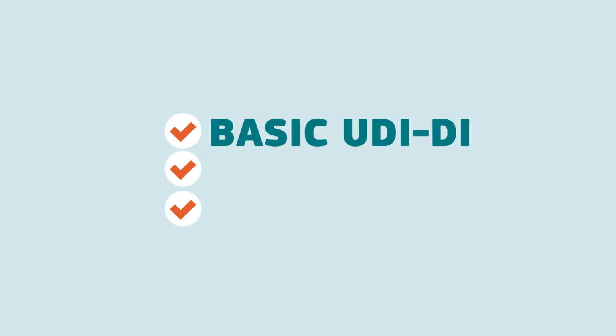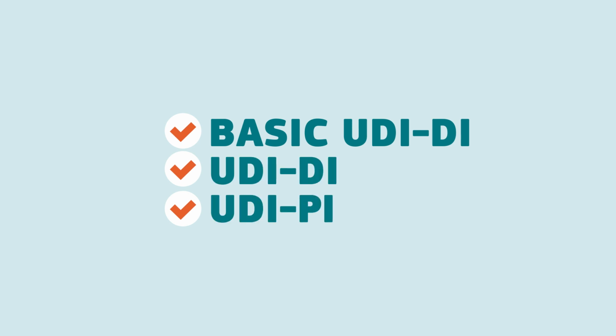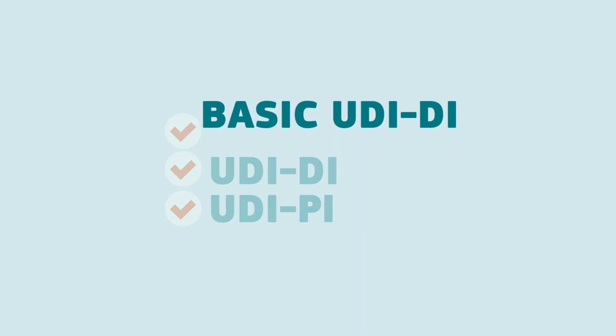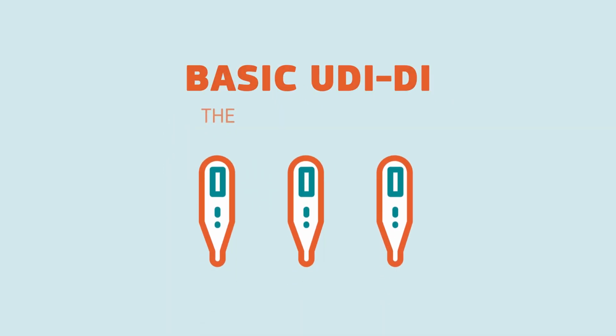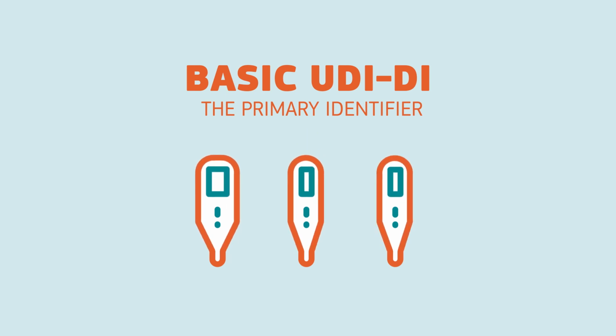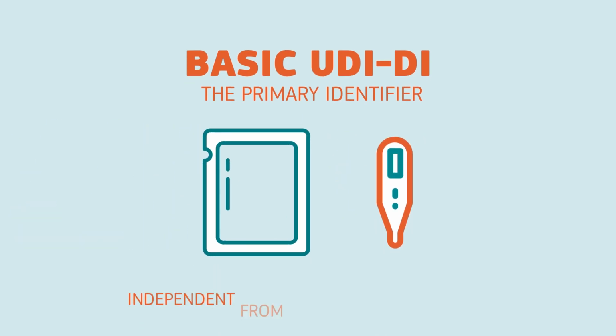The UDI consists of three core components: a basic UDI device identifier or basic UDI-DI, a UDI device identifier or UDI-DI, and a UDI production identifier or UDI-PI. Let's take a closer look at what each of these mean. The basic UDI-DI is a primary identifier for devices with the same intended purpose, manufacturer, risk class, attributes, and essential design. It is independent from the packaging or labeling of the device.